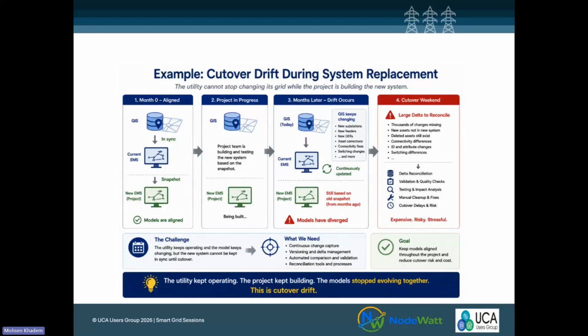Challenges: the utility keeps operating and the model keeps changing, correct? As I said, they are not stopping. They add new equipment to your grid, but the new system cannot be kept in sync until cutover. The process isn't there for everything to stay in sync and live updated. Before you go live, you stop it, get a snapshot, run all your testing, go through all your test cases for topology and power flow and so on. On cutover day, you need to get the new stuff inside the system to have a complete system. Otherwise, you are partially operating the system.